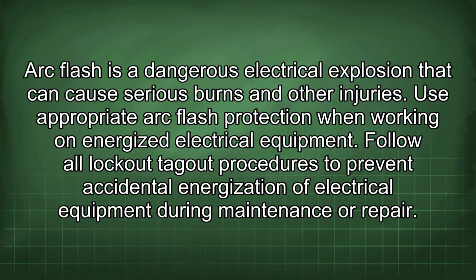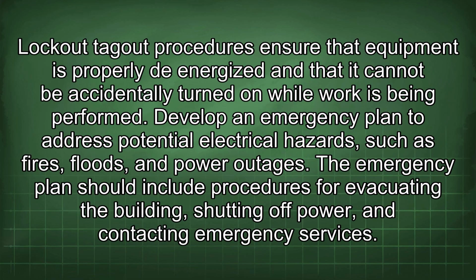Follow all lockout-tagout procedures to prevent accidental energization of electrical equipment during maintenance or repair. Lockout-tagout procedures ensure that the equipment is properly de-energized and that it cannot be accidentally turned on while work is being performed.